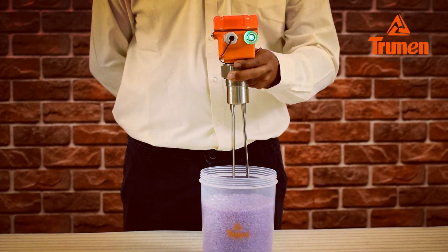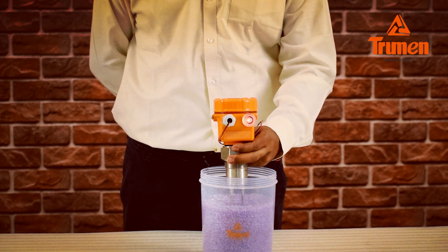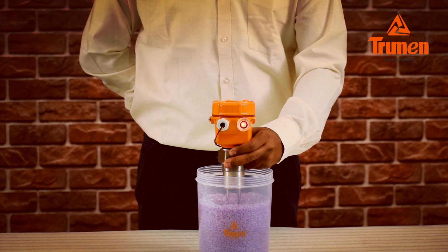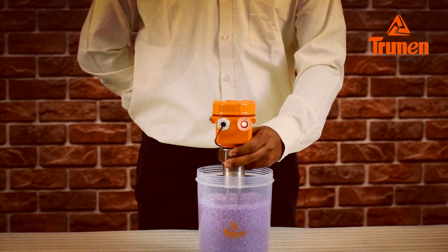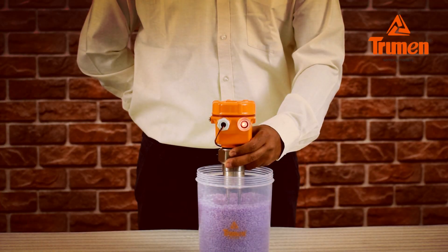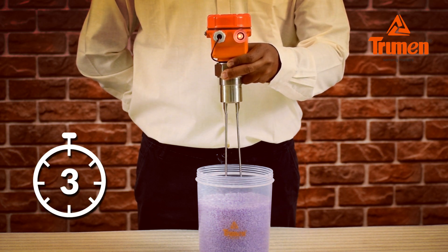The Trumen vibrating fork level sensor starts vibrating in air. The power LED is on and the status LED is off. Now we fill the material — solids, granules, or powder — up to the fork's level. You can see the status LED of the LSV turns on, meaning material has reached the high level. The relay status also changes from NC to NO. Dry delay is set via dip switch number 2 — turn on switch 2 and empty the material; the LSV waits for 5 seconds before generating switching.